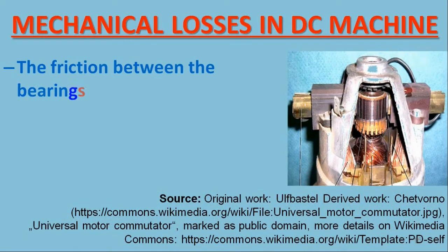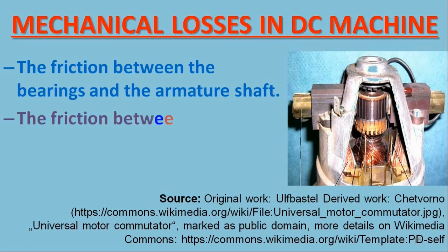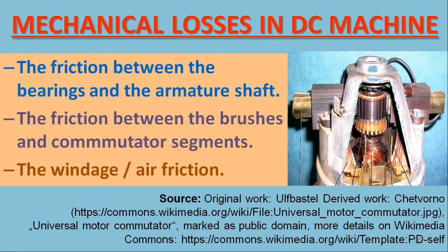Mechanical losses in DC machines: The mechanical losses in the DC machine are due to the friction between the bearings and the armature shaft, the friction between the brushes and commutator segments, and the windage or air friction. To reduce the friction loss caused by armature rotation, the bearings are usually lubricated. Note that the mechanical losses depend on the speed of the DC machine; however, for a given speed, these losses can be considered constant.